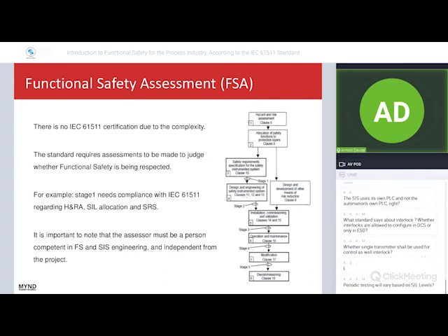The last point that I would like to speak about is the functional safety assessment. I already told you that there is no certification for 61511 because it's very, very complicated for a certification body to certify one safety instrument function. The standard requires what is called the functional safety assessment by a functional safety assessor, during different stages: stage 1, after the safety requirement specification; stage 2, after SIL verification; stage 3, after commissioning and SIS validation; and then stage 4, stage 5.